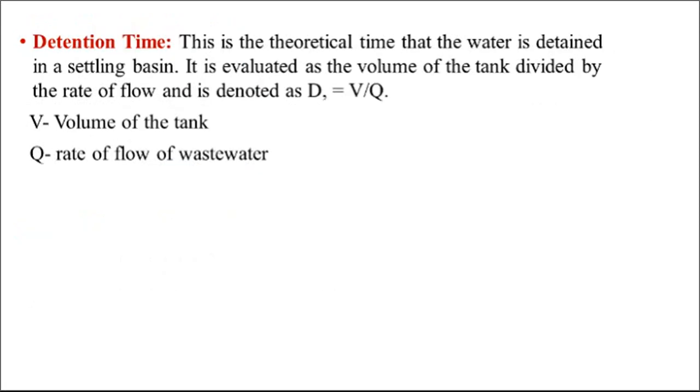And the third important term is the detention time. It is the theoretical time that the water is detained in a settling tank. It is evaluated as the volume of the tank divided by rate of flow and is denoted by capital D or dt. So detention time D is equal to V by Q, where V is the volume of sedimentation tank and Q is the rate of flow of wastewater.